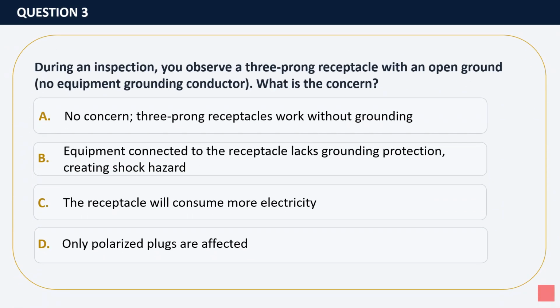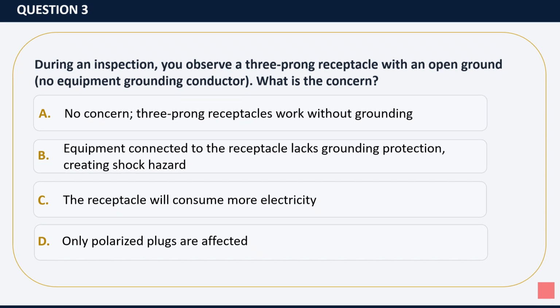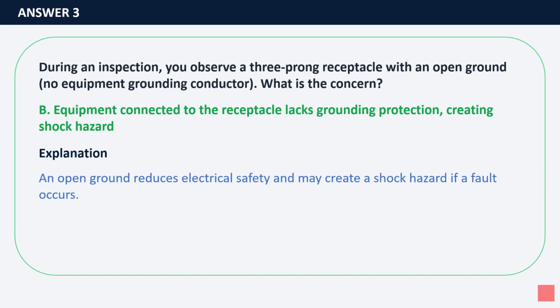Question 3. During an inspection, you observe a 3-prong receptacle with an open ground, no equipment grounding conductor. What is the concern? A. No concern. 3-prong receptacles work without grounding. B. Equipment connected to the receptacle lacks grounding protection, creating shock hazard. C. The receptacle will consume more electricity. D. Only polarized plugs are affected. Answer B. Explanation: an open ground reduces electrical safety and may create a shock hazard if a fault occurs.